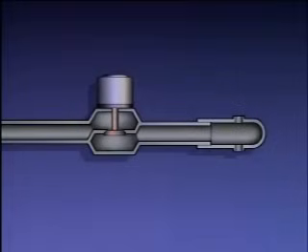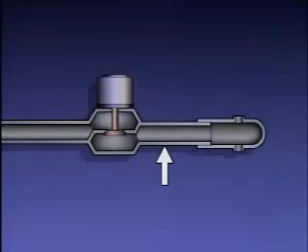During the operation of most boilers, especially coal-fired boilers, soot builds up on water wall tubes and other components. This soot buildup blocks efficient heat transfer and must be removed if efficient boiler operation is to be maintained. Soot blowers remove soot by blowing it off of the tubes with a medium such as compressed air or steam. A typical soot blower is made up of a lance tube with nozzles, a feed tube, and a valve.